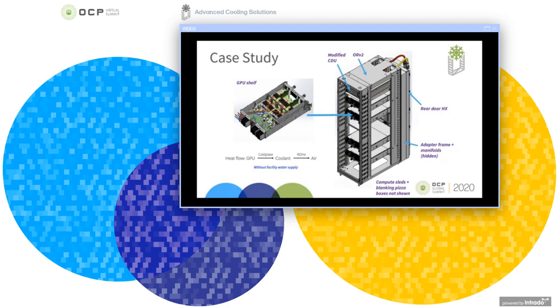So the heat that was absorbed by the cold plates that were attached directly to the GPUs was exhausted by the rear door heat exchanger through the air that was exhausted by the IT gear approaching it. As you can see, this forms a closed loop solution, and therefore the rack is 100% air-cooled.